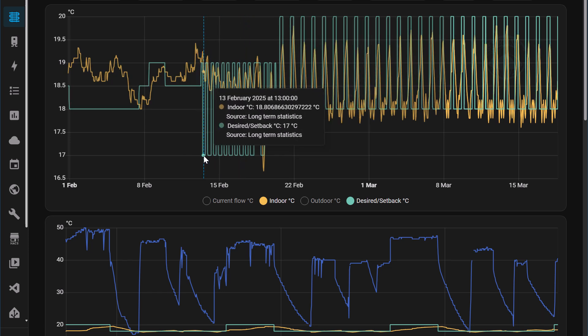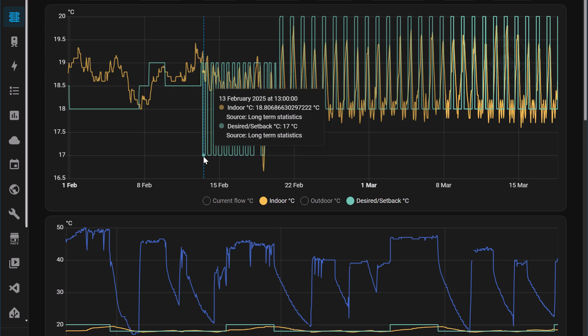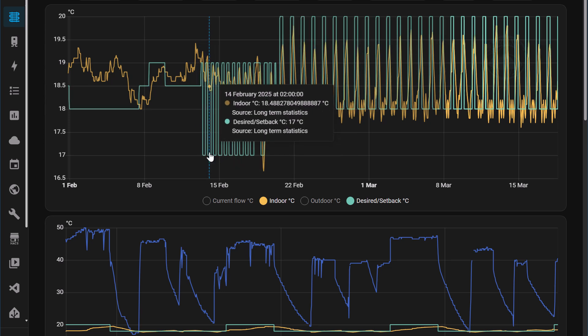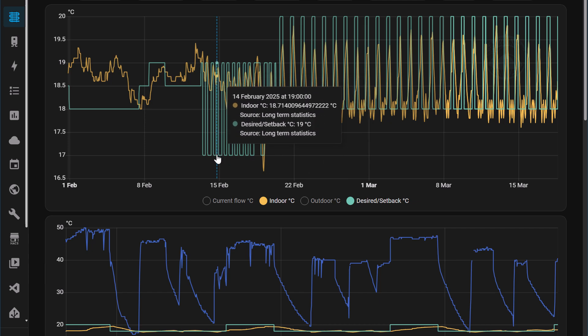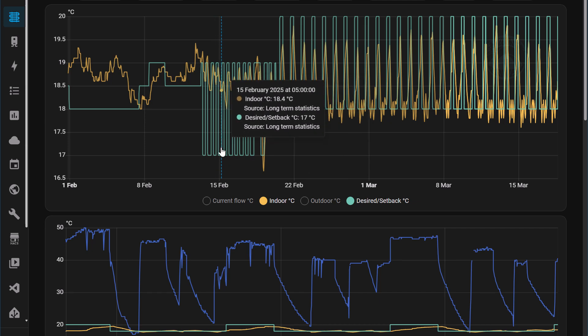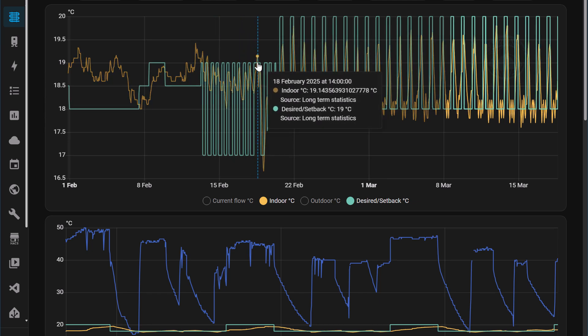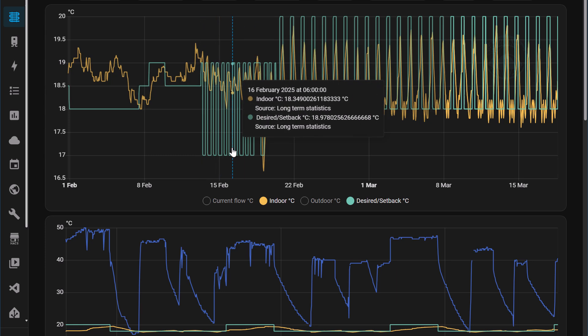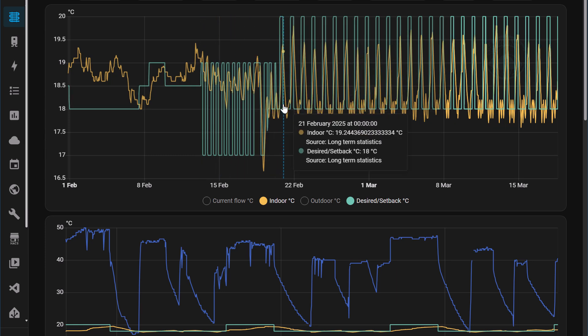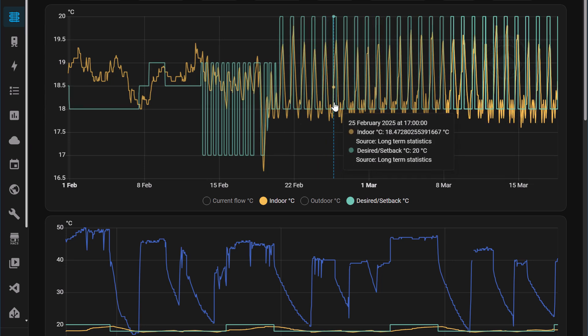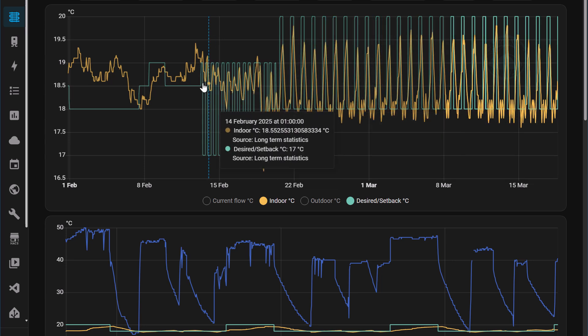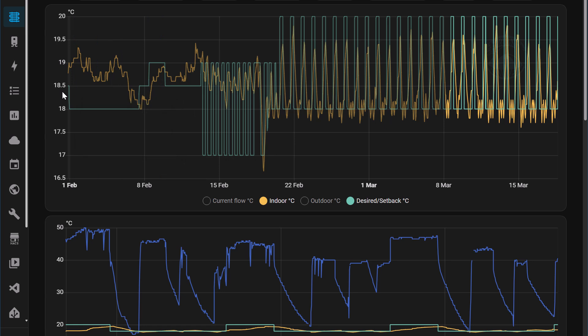In hindsight as well, setting the setback temperature to 17 and the desired to 19 is a little silly because you'd never want your indoor temperature to drop down to the setback temperature because then it'll take too long to get back to the desired temperature. This is something that you'll see when I talk about the next room temperature mod expanded. This is what I've changed and what I concluded was a mistake in these previous tests.